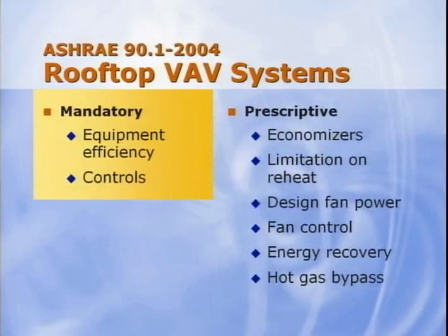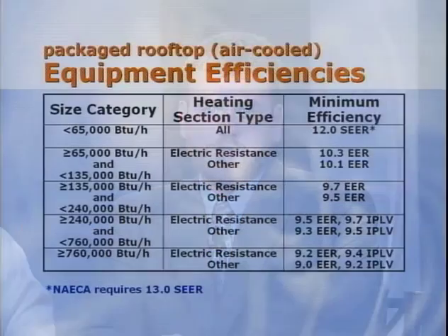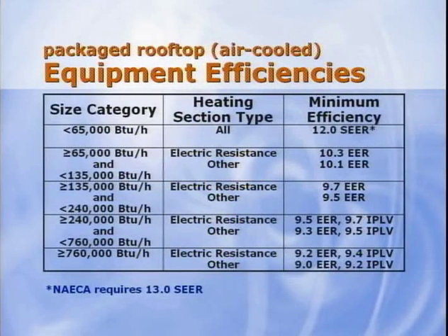Starting with ASHRAE 90.1, we'll cover a number of the mandatory and prescriptive requirements of the standard that apply specifically to rooftop VAV systems. I'll be the first to admit that this is not an exhaustive list, but applies to general rooftop systems. For example, an office space, school, or medical office building. Now let's look at those mandatory requirements. Our slide shows minimum equipment efficiency requirements for packaged rooftops.